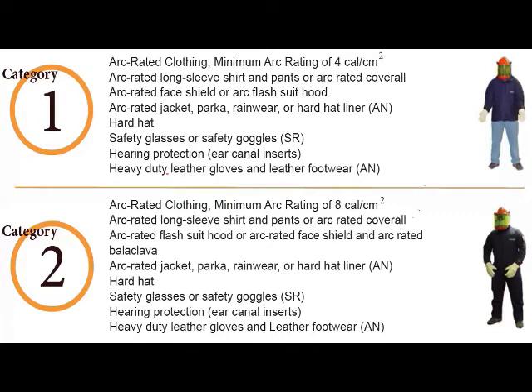For arc flash, there are normally 4 categories of PPE recommended. The first is a basic category calculated for 4 calorie injuries, where normal cotton pant and shirt, or an arc rated coverall for 4 calorie with a face shield, can be used.